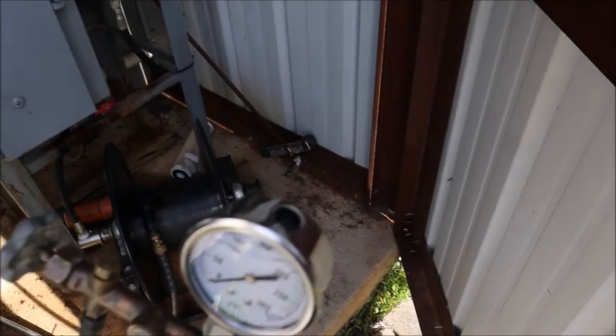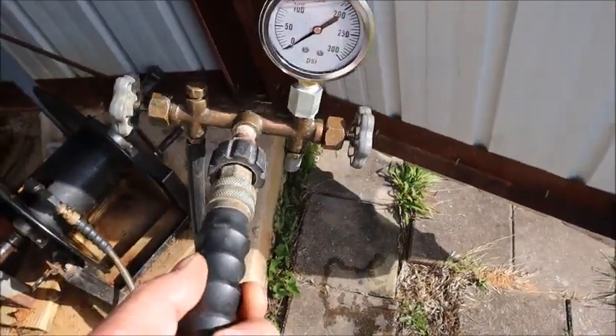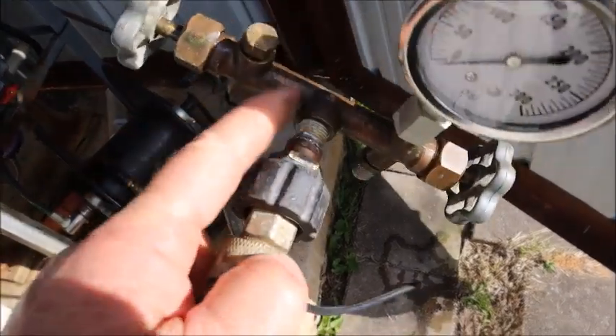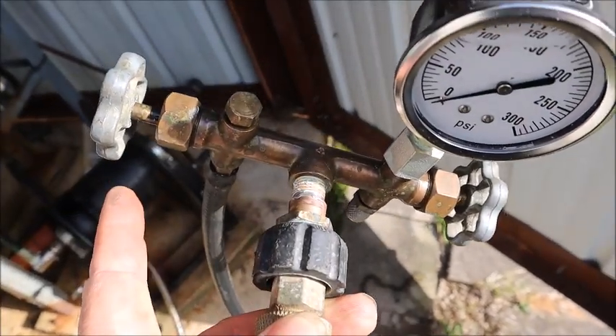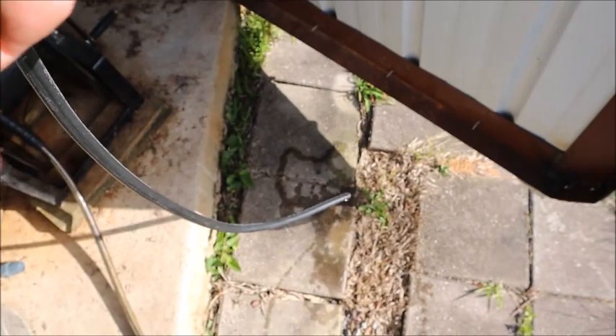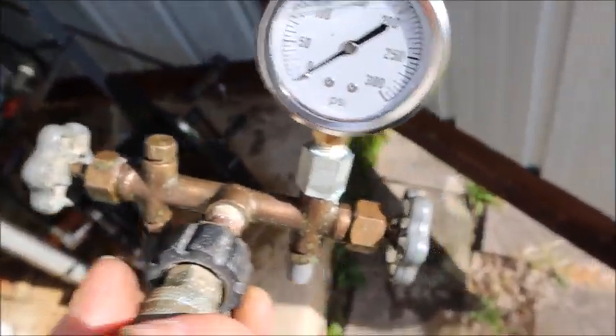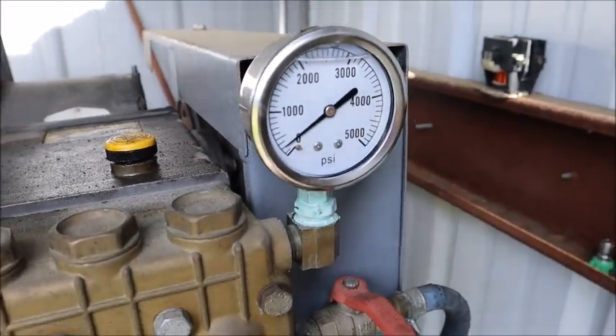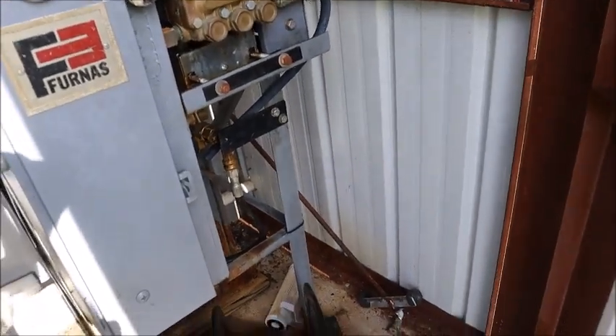Howdy folks, fixing to do a hydro test on an air compressor tank. I've got this rig built up here — we'll class this as an adapter, which goes from a pressure washer to a refrigerant gauge manifold. This valve here is a bypass valve that just dumps water; the connection here will go to the tank we're testing. By manipulating those valves I can create a very controlled amount of pressure, up to the limit of the pressure wash pump, which will unload at about 5,000 pounds.